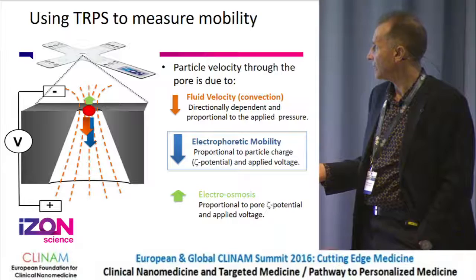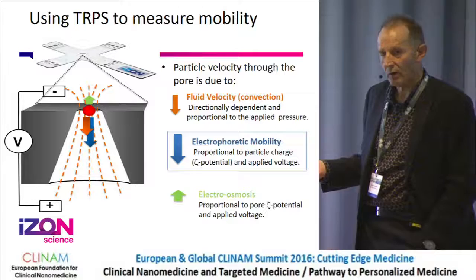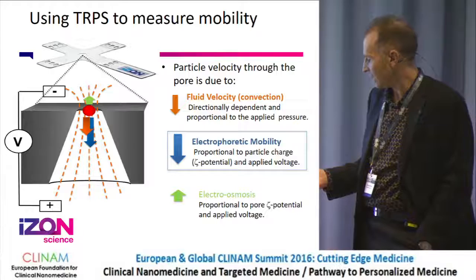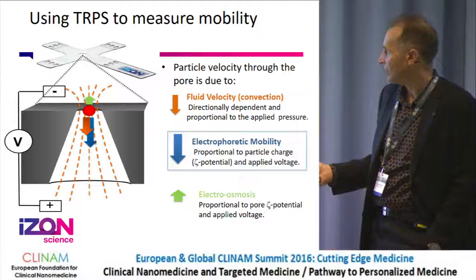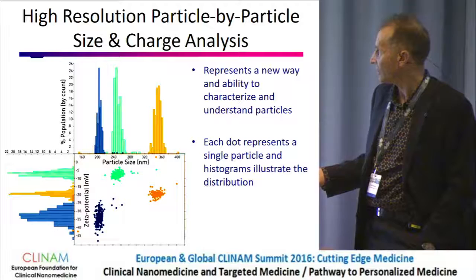This is how TRPS measures electrophoretic mobility. You've got a particle going through a hole one by one — it disrupts the current. We're looking at three components that drive the velocity: fluid flowing through the hole (convection), electrophoretic mobility of the particle, and electroosmosis — which is the counterflow of ions up the side of the hole. We measure in a very detailed way the velocity of the fluid and particles to extract the electrophoretic mobility of each particle as it goes through the hole.